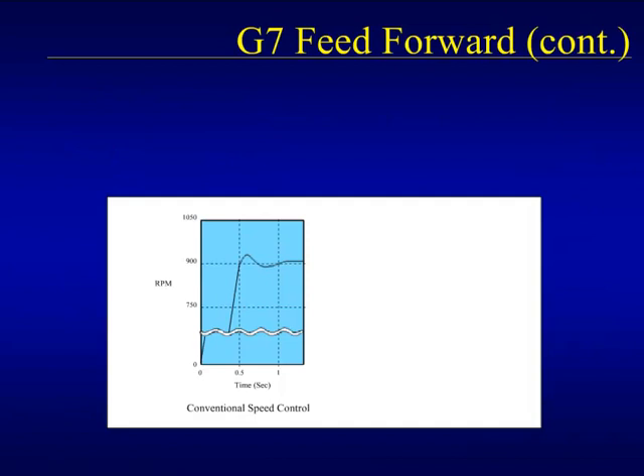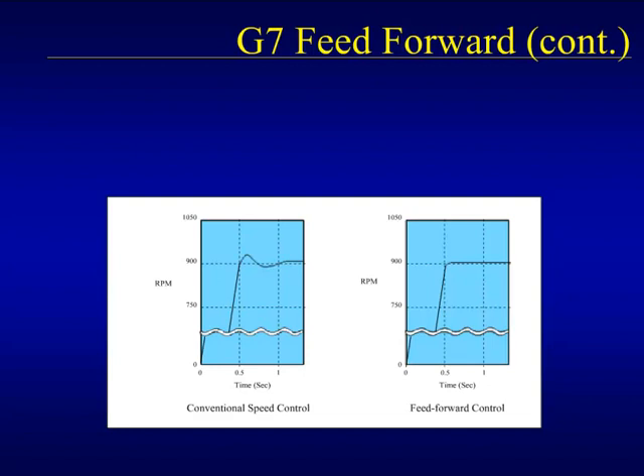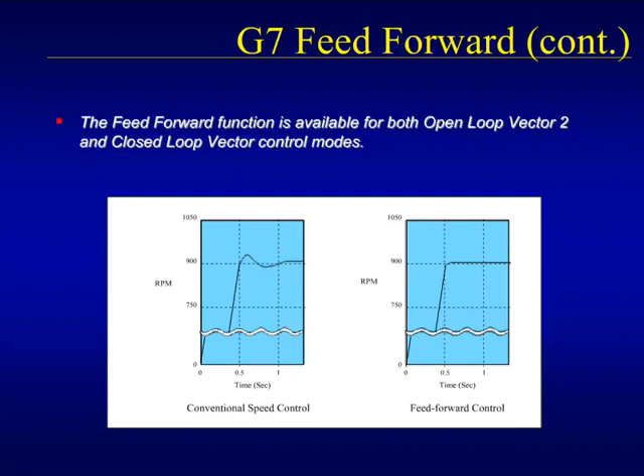In the case of a stepped change in the frequency reference, the ASR will cause some overshoot and ringing of the output speed the way a normal PI loop will. The feed-forward function compensates for integral windup in the ASR and also variations caused by the motor's inherent time constant to keep the output speed from overshooting the frequency reference. Use the feed-forward function featured in the open-loop vector 2 and closed-loop vector modes of the G7 as a potential solution to many positioning applications.